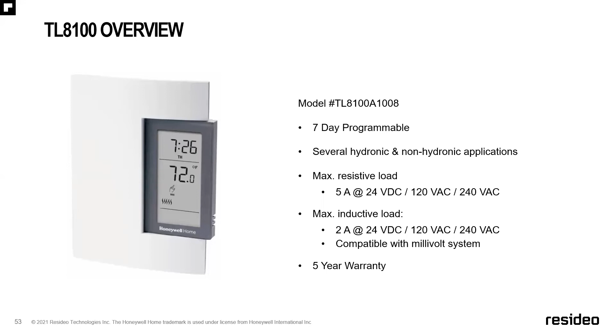For hydronic applications, the TL8100 has pump protection modes to prevent seizure and callbacks—it activates the pump for 1 minute every 24 hours to make sure nothing clogs up or seizes. It works well with a single line volt circulator pump, 24 volt circulator pump relay, for example our R889A as well as the R8845Us, our 24 volt zone valves including the 1000 and 5000 series, and then 120 volt zone valves as well, such as our V4044s.